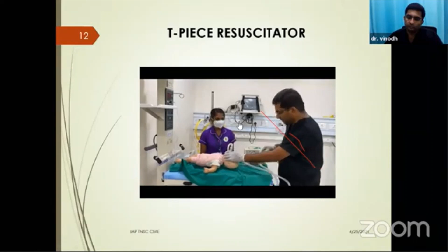This is the maximum pressure limit beyond which we cannot deliver, and this is the port to adjust the peak inspiratory pressure, PIP, that we are supposed to deliver. Once we close it over the baby's mouth and nose, when it snugly fits, the amount of PEEP that has been delivered will be displayed here. The PEEP can be adjusted by rotating the valve over here. This is how a T-piece resuscitator works.